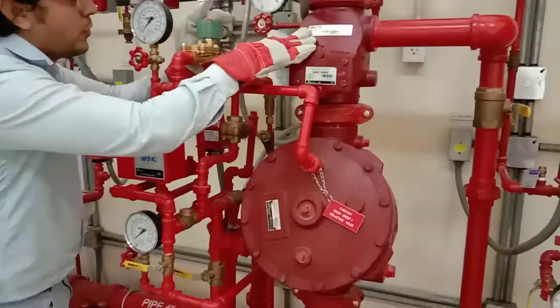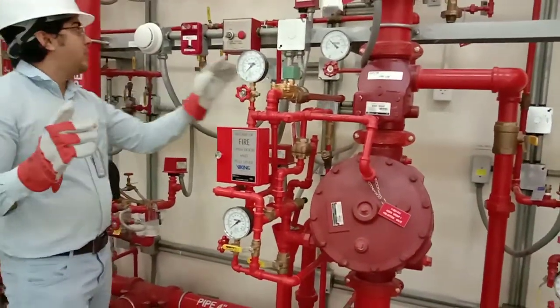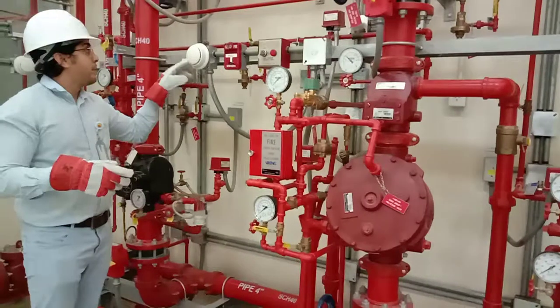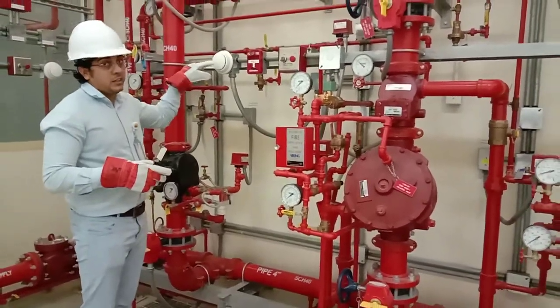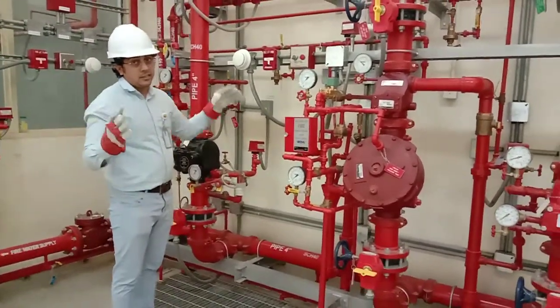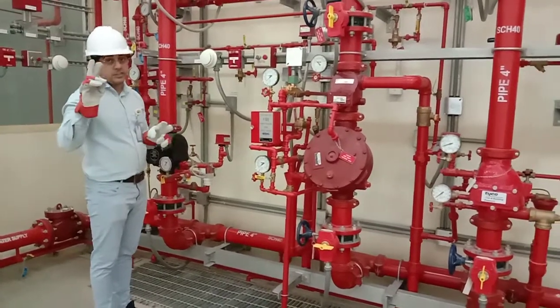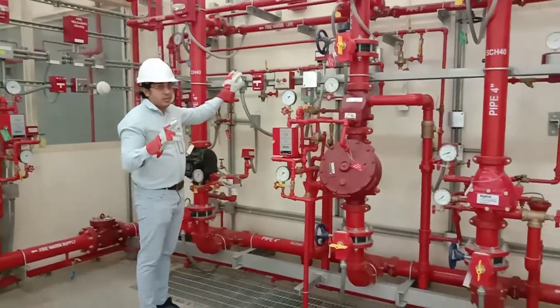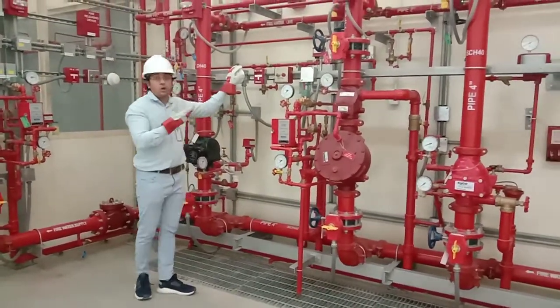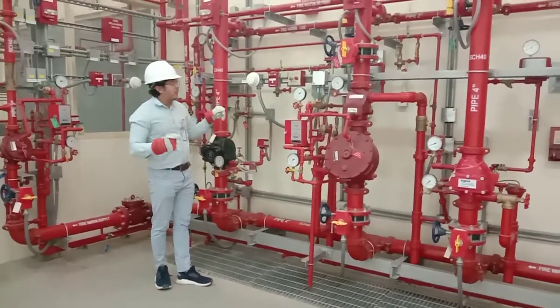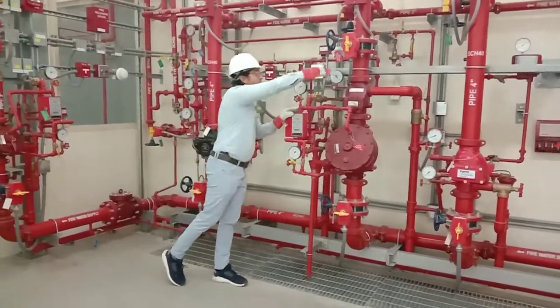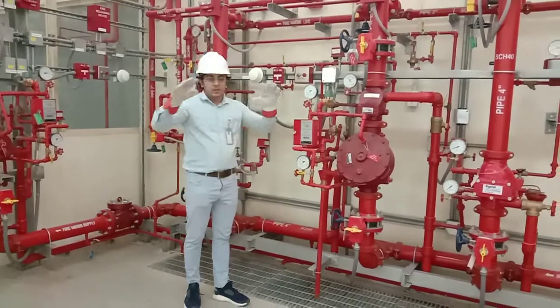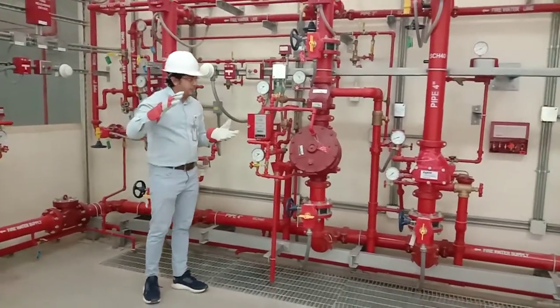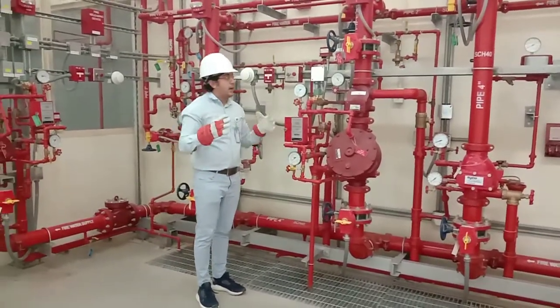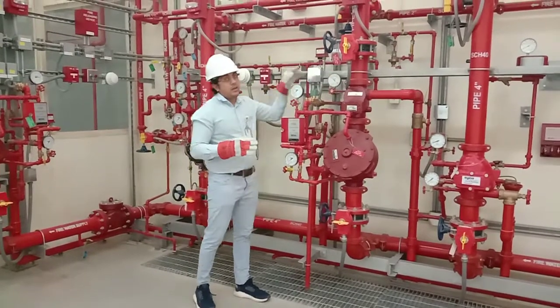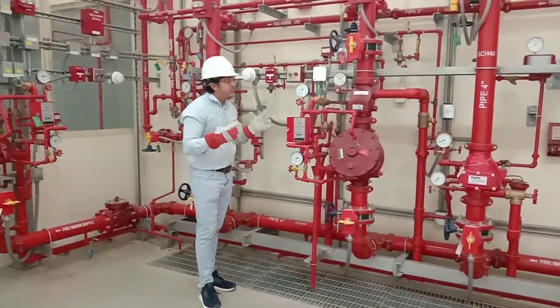inside the system. So for the double interlock system, either the sprinkler activates or the detector activates, it will not allow water discharge into the system because they need two detections. If this one activates by mistake due to some false smoke in those areas, there will be no water discharging into the system because the sprinkler is already closed and it is pressurized by the air. This is all about the pre-action system.